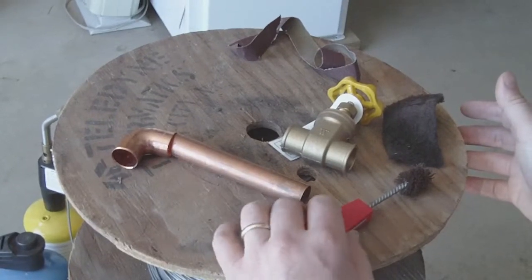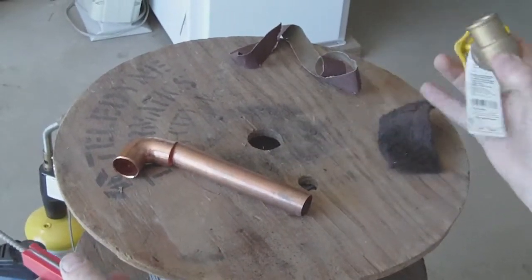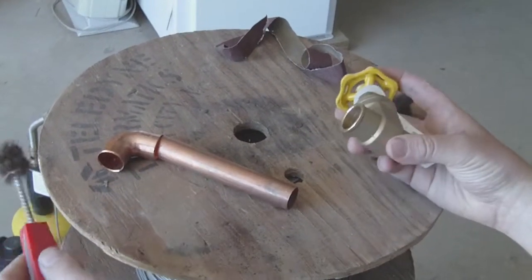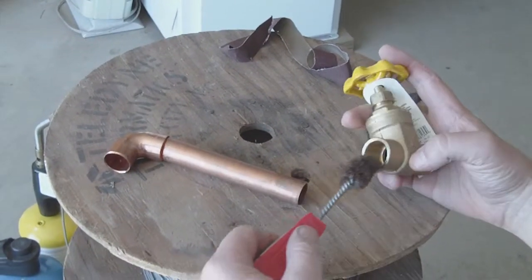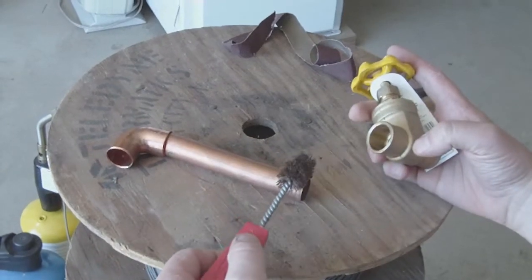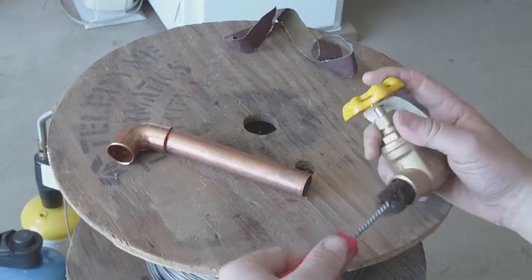The absolute most critical component of making a successful solder joint is the cleanliness of the fittings before they get sweat soldered. If there's any corrosion on any piece, the flux and the solder will not adhere to it and will have problems.